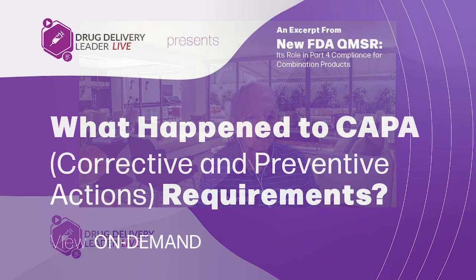So the verification is to make sure that the corrective action does not adversely affect the ability to meet the applicable regulatory requirements, notice that, or the safety, which is the risk management part, and performance of the device. So the standard requires you to take some additional action before you implement that corrective action. And then you need to go back and do the same thing again because you're going to verify that it was effective after it's implemented. So there's a repetitive step in there because of the fact that, especially on the FDA side, a big finding over the years is that it hasn't been implemented properly.